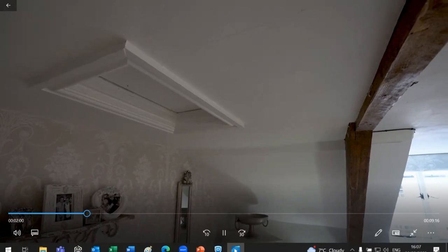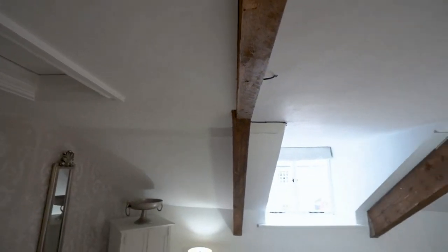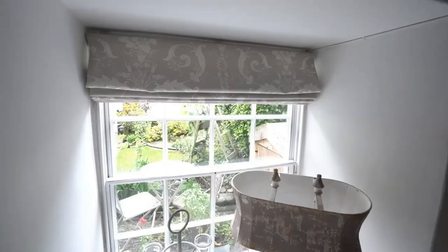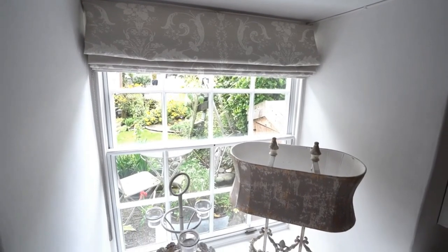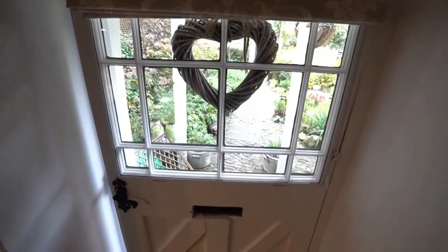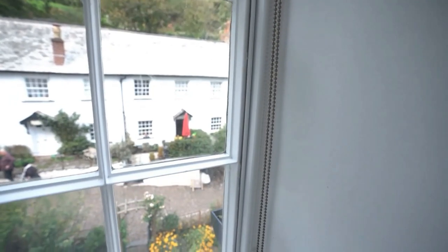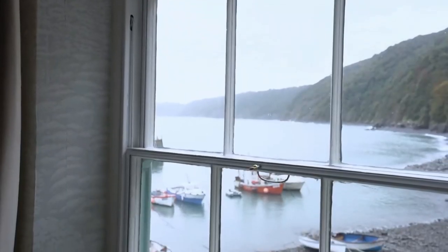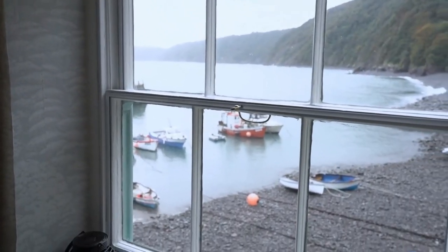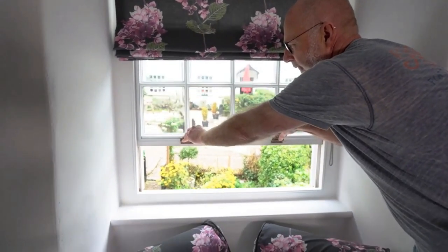We topped up the loft insulation from 100 to 300 millimetres. We installed elegant, very durable and concealed brushes in the doors and windows which sealed up the drafts. And we also installed our proprietary secondary glazing system called cozy glazing. Now, cozy glazing is unique because it's made of plexiglass fitted onto the windows with magnetic tape. And so it's actually virtually invisible when in place.